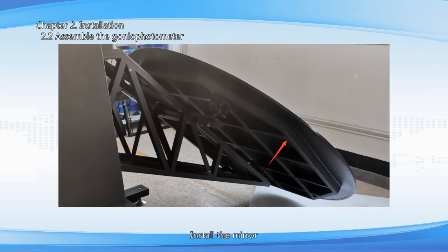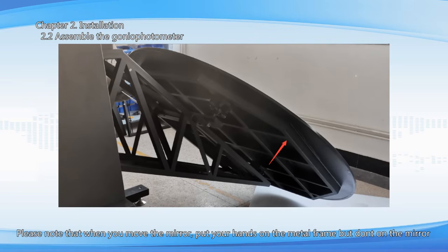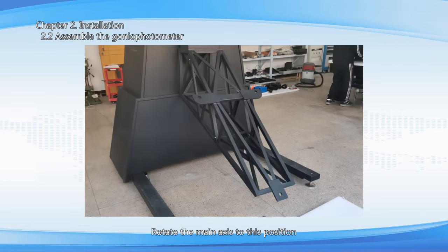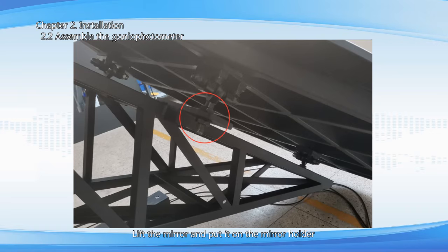Install the mirror. Please note that when you move the mirror, put your hands on the metal frame but don't touch the mirror. If you touch the mirror, you may break it. Rotate the main axis to this position. Lift the mirror and put it on the mirror holder. Make sure the 3 screws on the mirror align with the 3 screw holes. Lock the 3 sets of screws as shown in the figure.